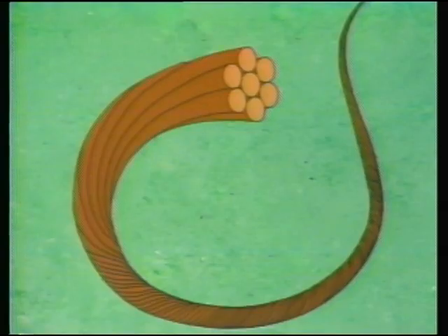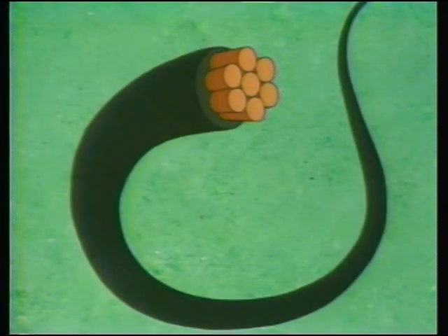First, there's the conductor, which in this case is a stranded copper wire. Typically, primary conductors are made of stranded copper or aluminum wire. Conductors can also be solid wire, but since solid conductors aren't as flexible as stranded conductors, they're seldom used for URD cable applications. Directly over the conductor is a conductor shield. This is a layer of semiconductor material that encloses the conductor to help give it a more uniformly round shape. We'll see why this uniformity is important a little later on.